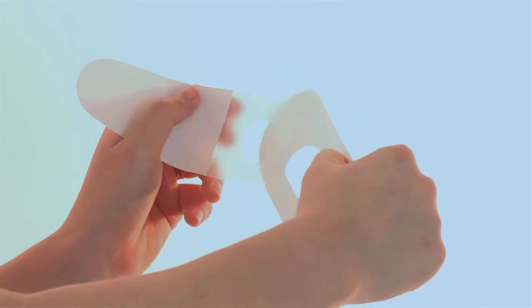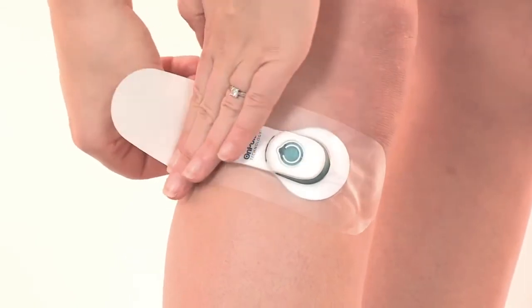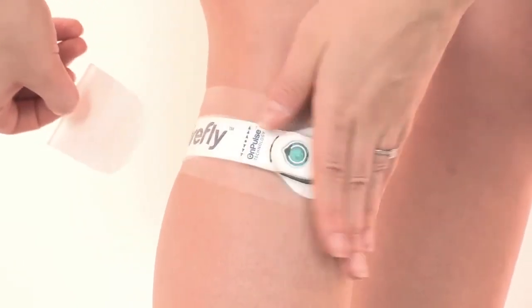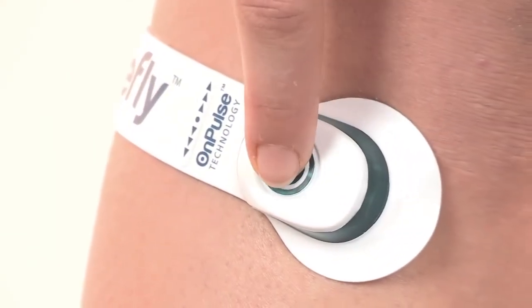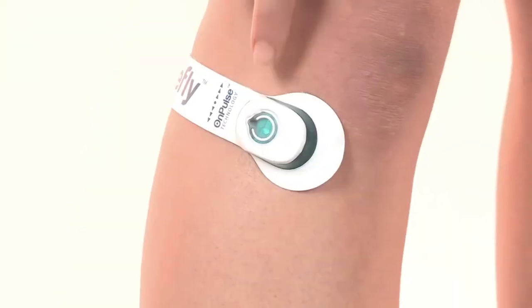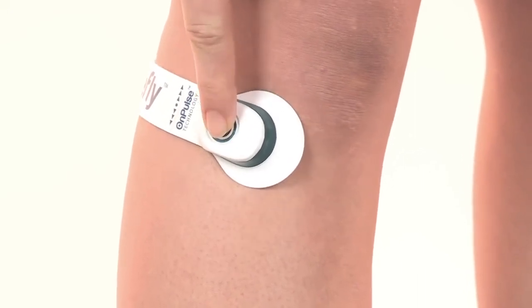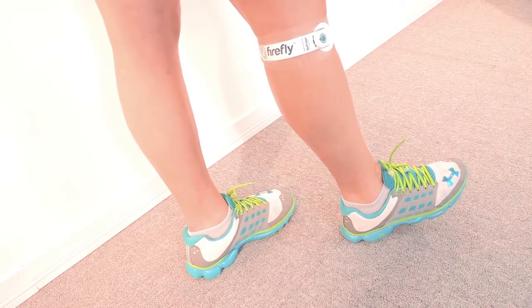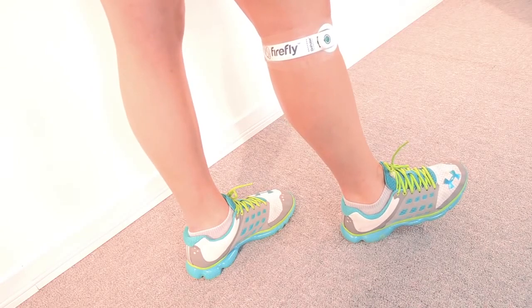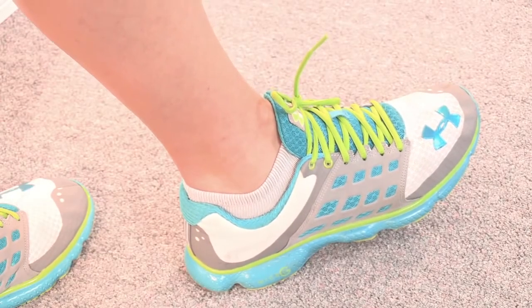For additional adhesion, if required, apply one of the supplied adhesive strips over the device. Once in position, use one short click of the button — one second — to activate the device, and further short clicks to set the appropriate level. With the heel to the ground and the front of the foot raised, look for a discernible movement of the muscles in the lower leg and a visible outwards movement of the foot. It is not sufficient to see only a slight movement in the muscles of the lower leg alone. The movement in both the lower leg and foot should be discernible.